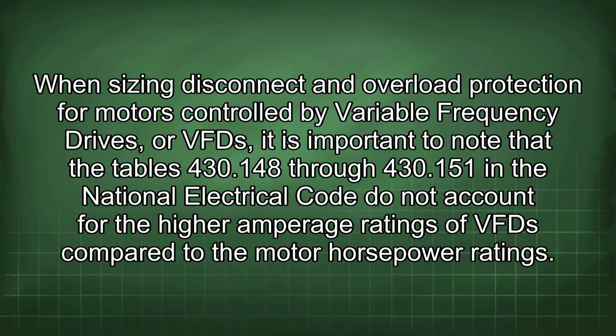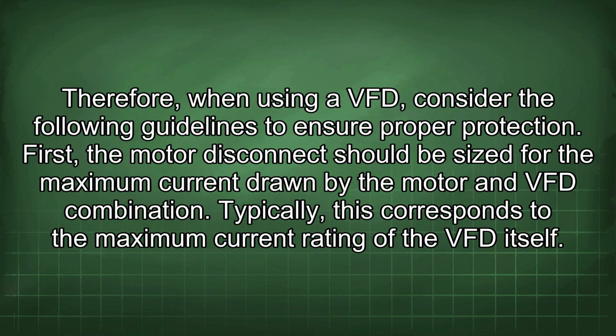When sizing disconnect and overload protection for motors controlled by variable frequency drives, or VFDs, it is important to note that the tables 430.148 through 430.151 in the National Electrical Code do not account for the higher amperage ratings of VFD compared to the motor horsepower ratings. Therefore, when using a VFD, consider the following guidelines to ensure proper protection.